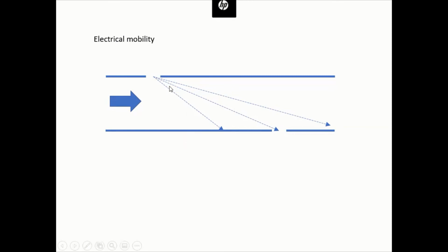That's going to classify particles of, let's say, several hundred nanometers. After they are classified, they can be introduced into this condensation particle counter, so we can measure the number of particles with this size.